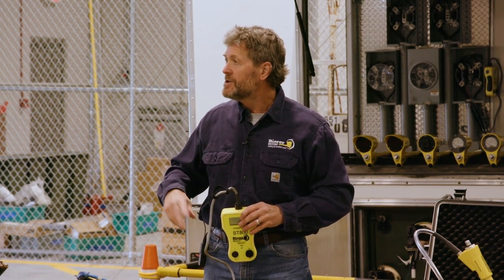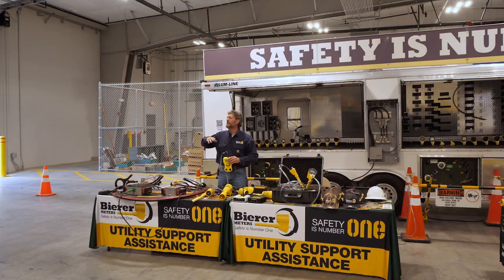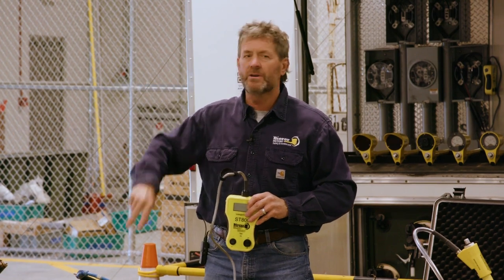You're hoping that when you go to the load, you'll see those counts jump up fast and furious, because you saw 240 and you're hoping the integrity on both legs is good. Sure enough, you turn it on and it goes to the load, and you're seeing 14 or 16, maybe 12 amp jumps per count. It gets up to about 800 amps, stops, holds the count. Those two legs are good.